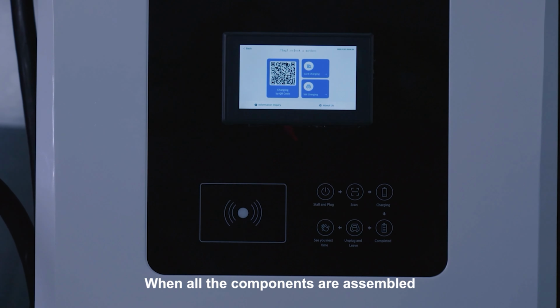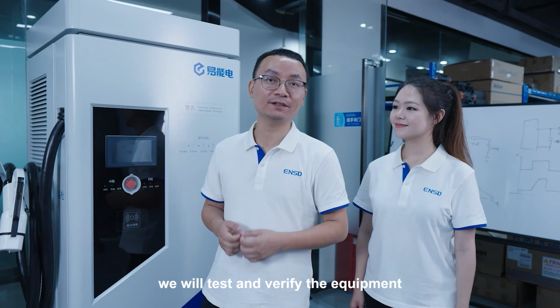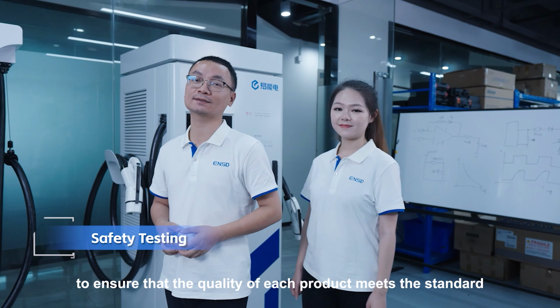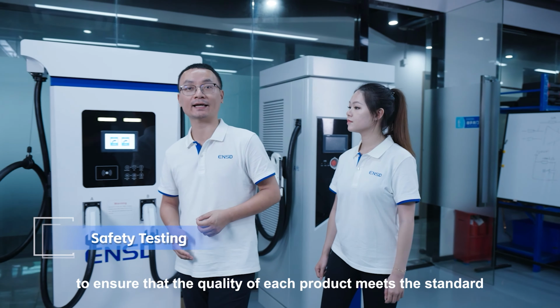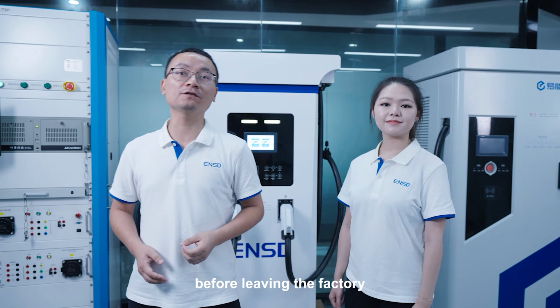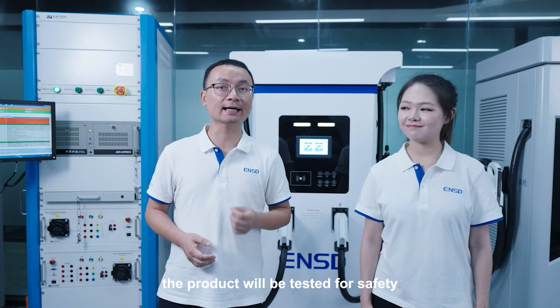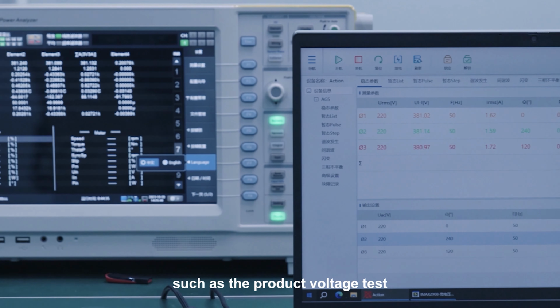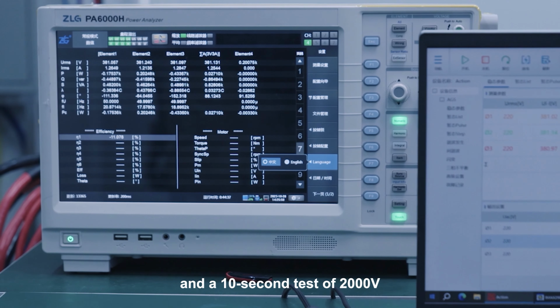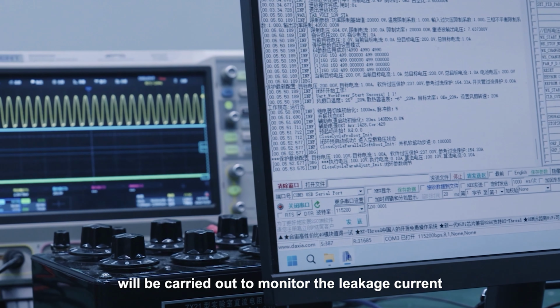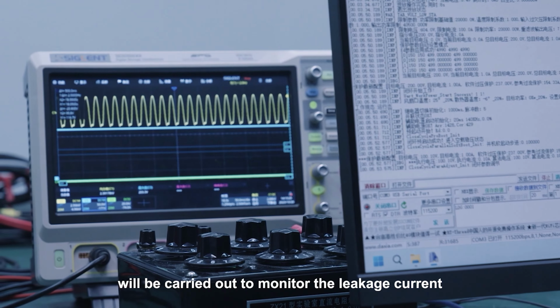When all components are assembled, we test and verify the equipment to ensure each product meets the standard. Before leaving the factory, the product undergoes safety testing, such as a product voltage test with a 10-second 2kV test to monitor leakage current.